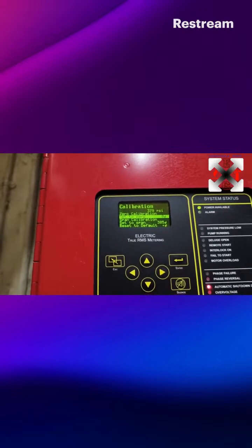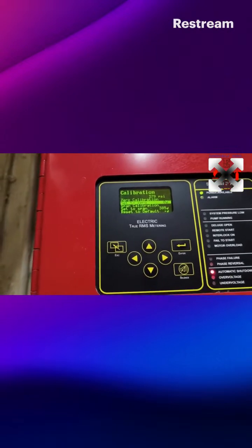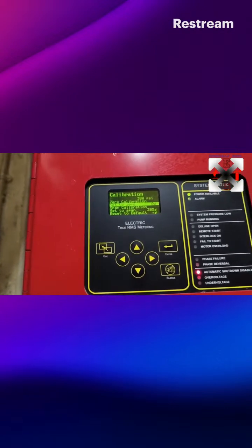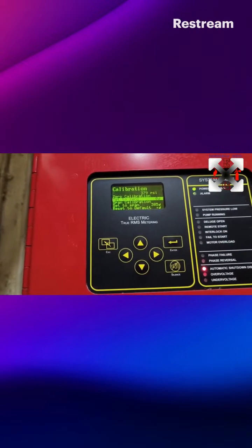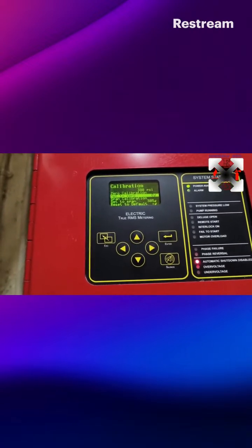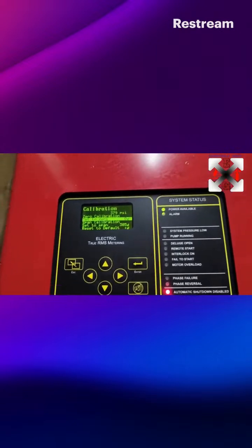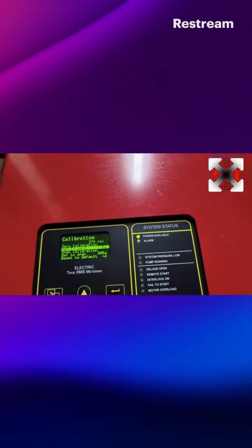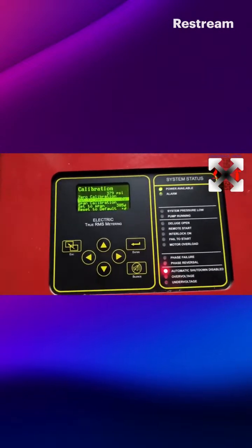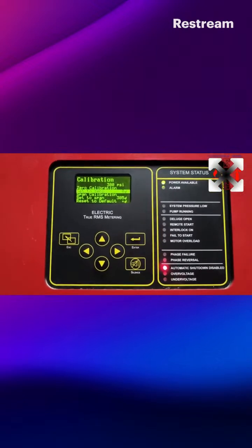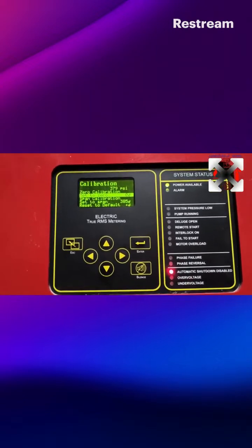So then we will have the same pressure. Okay, it will be very awkward when you see that the jockey pump is showing like 385 and this is showing like 360. It's quite a margin, right? So then it will just cause a whole lot of issues setting up the cut-ins and the cut-outs. So what we're gonna do here now, let's see.